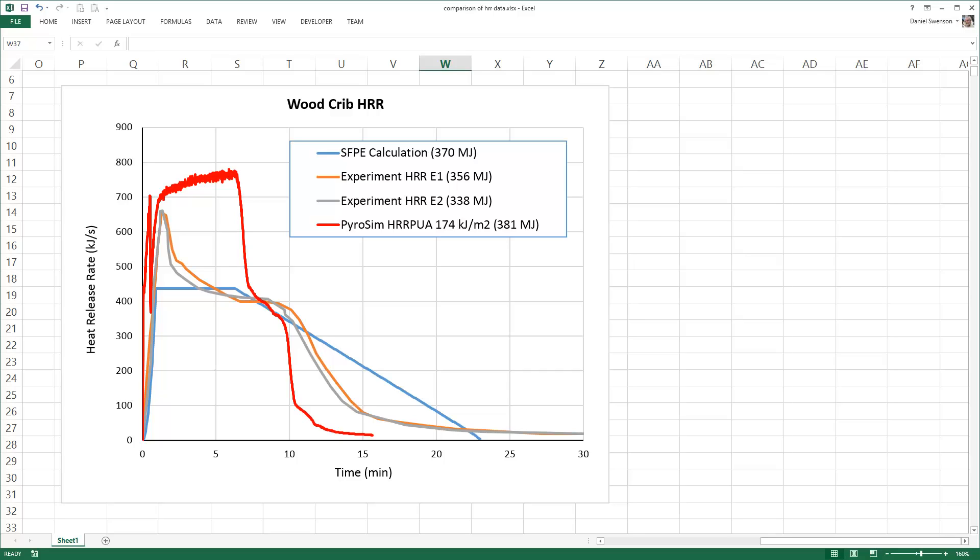In addition, the experimental results show an initial peak followed by decay, where the calculated results actually increase with time. We need to repeat the calculation with a surface heat release rate that follows this peak and decay pattern as shown in the calorimeter data.